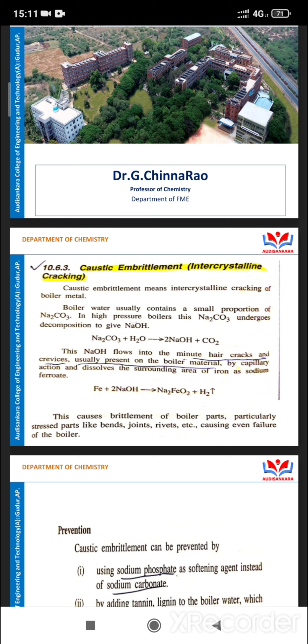And next, how to prevent it? What are the remedies for caustic embrittlement? One thing is, caustic embrittlement can be prevented by using sodium phosphate as a softening agent instead of sodium carbonate. And the second is by adding tannin and lignin to the boiler water, which blocks the hair cracks. That is the prevention of caustic embrittlement or intercrystalline cracking.